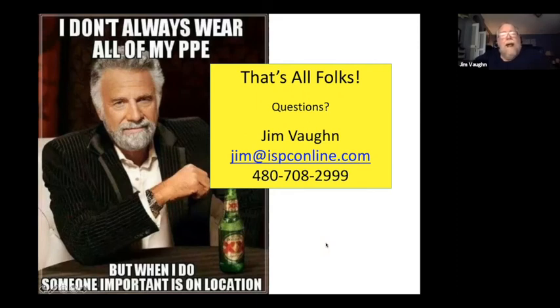See, here's the problem. Outside of the hose, you're not working there. You're working inside of the hose in the gap or in the area that you're in. So you have to think about this from the technical application viewpoint. You're only allowed to expose yourself when you're wearing rubber gloves to the work that you're actually doing. That conductor at the end of the hose is not your work area. So that conductor at the end of the hose is where you measure your MAD from. And if you can reach into that, or the tools that you're working with can, you can be in violation of MAD.